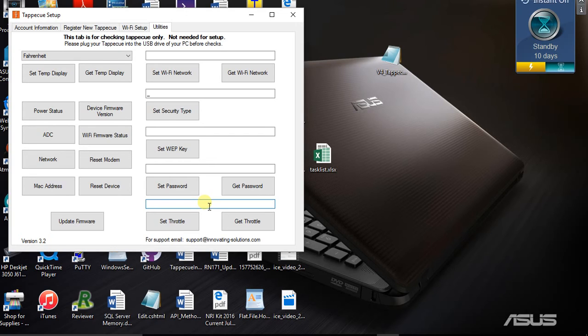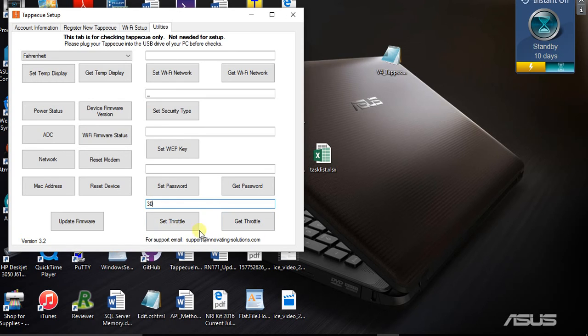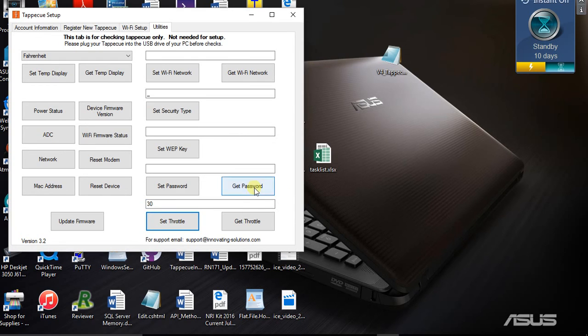Now, not all computers need to have the memory reset. Just the older versions are the ones that usually do. But for the sake of causing less problems, we'll just go ahead and reset memory. The first thing you're going to do is put a 30 right above this Set Throttle button, and you're going to click Set Throttle. What that does is it says in the memory that temperatures are going to be sent to the server every 30 seconds.